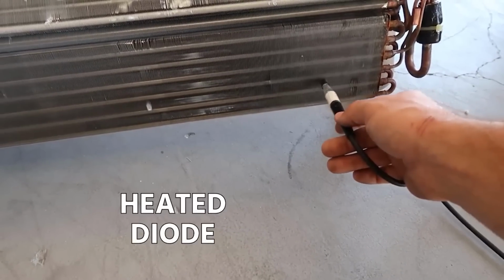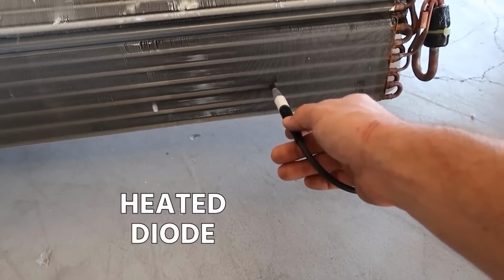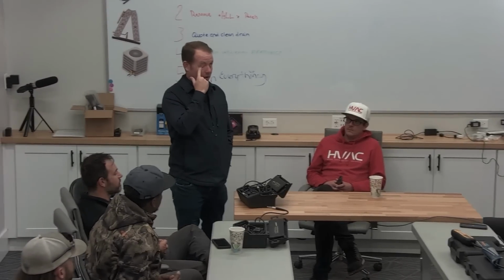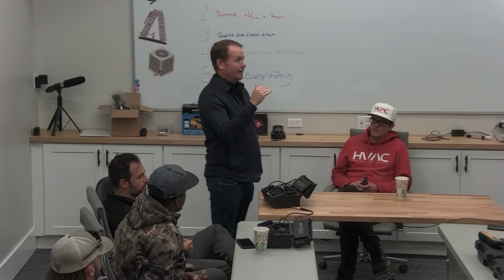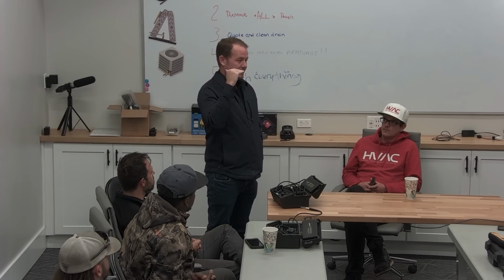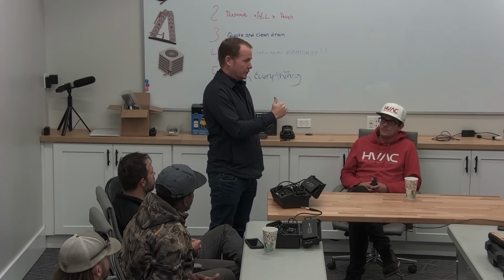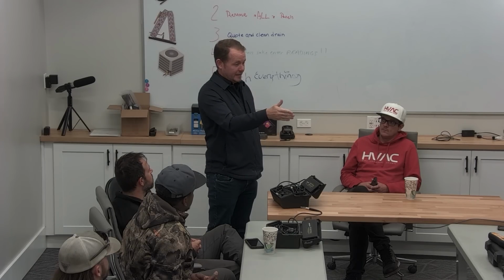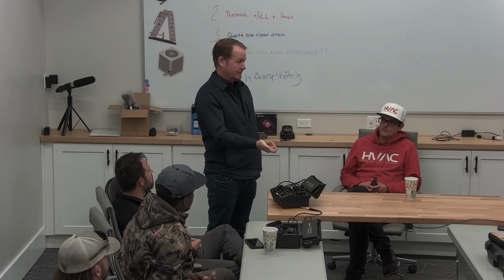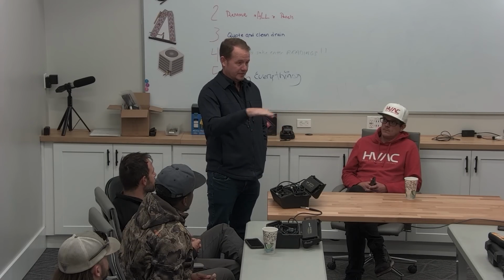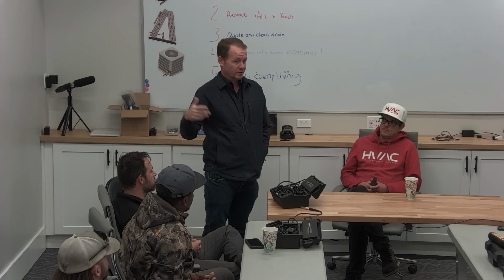This is a heated diode, some call it a heated pentode, same basic idea - you're heating it up and running the gas over it, and it's breaking it down, that's how it senses. Whereas with infrared, it doesn't have a base reference, so it's always referencing where you started out. So if you start it up in an already contaminated area, that's going to mess with the baseline, and you want to start it up outside.